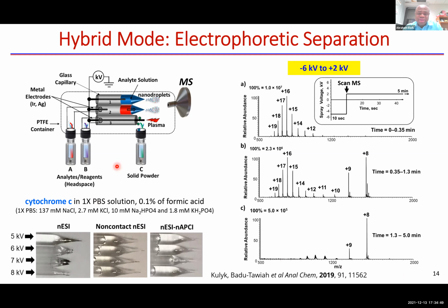That's a very good question. In fact, I know that Smith in Wisconsin has exposed protein ions to corona discharge, and he sees a charge reduction. That's possible, but I doubt that's what's happening here. When we start spraying, we are using about 2 kilovolts, and the breakdown voltage for air is actually 4 kilovolts. So when we begin to scan the mass spec and we are spraying, there's no discharge. The discharge only happens during the depletion regime.